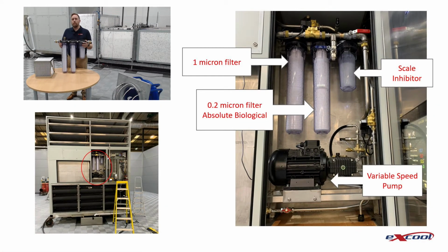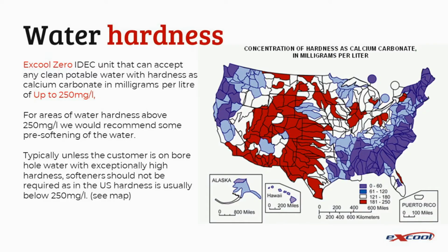The Excool Zero system has an onboard water treatment and storage system. By having it on board, we eliminate the capital and operational expenditure associated with centralised water treatment systems, such as reverse osmosis or water softening plant, and the treated water distribution and storage infrastructure. We simply require a pressurised mains water supply to each unit.